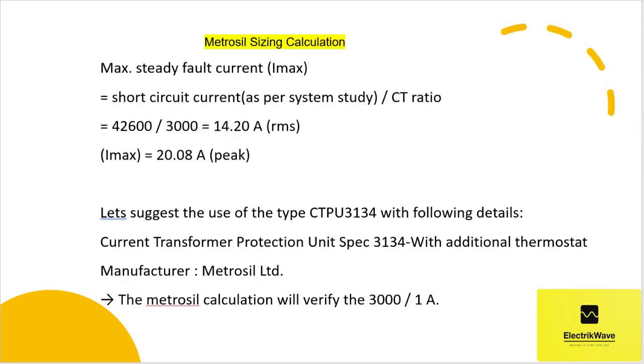Next. Now let's calculate the maximum steady fault current. Imax is equal to short circuit current over CT ratio, which is equal to 42,600/3000, which is 14.20 ampere RMS. Imax is equal to 20.08 A peak. Let's suggest the use of the type CTPU 3134 with the following details. Current transformer protection unit specification: 3134 with additional thermostat. Manufacturer, Metrosil Ltd. The Metrosil calculation will verify the 3000/1A.